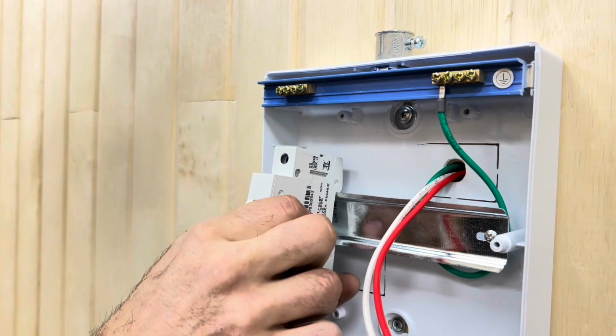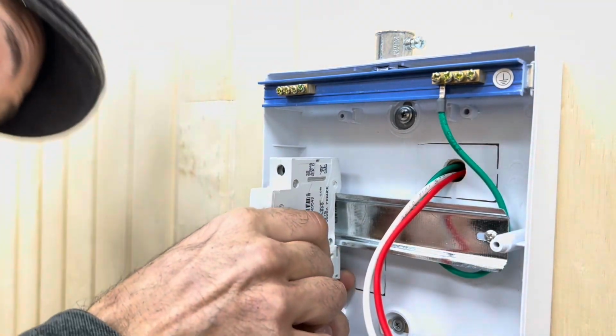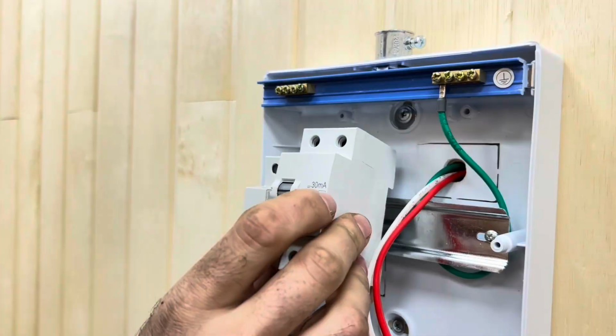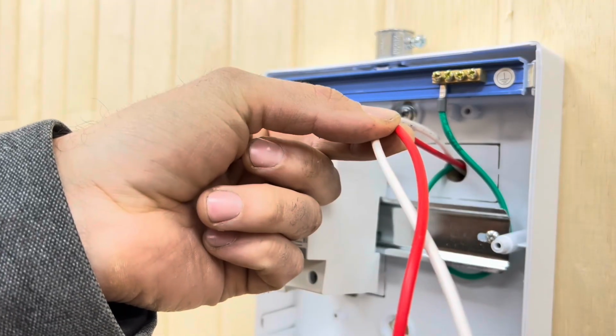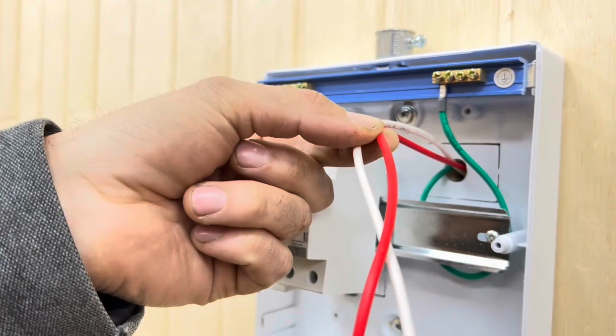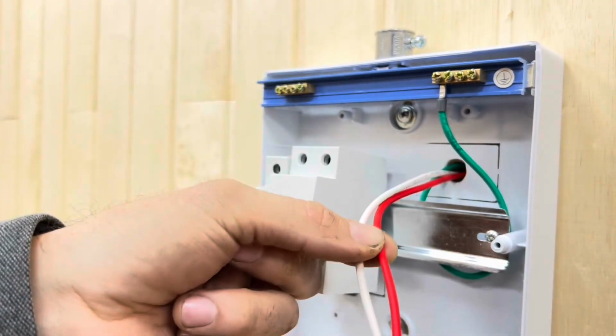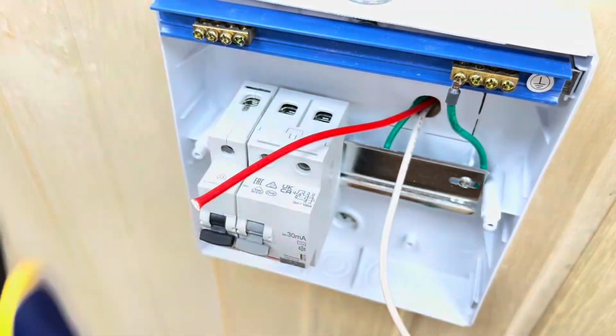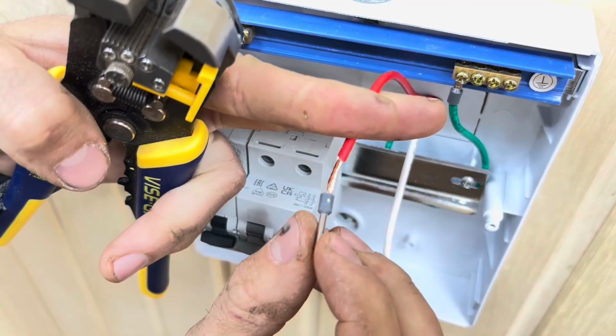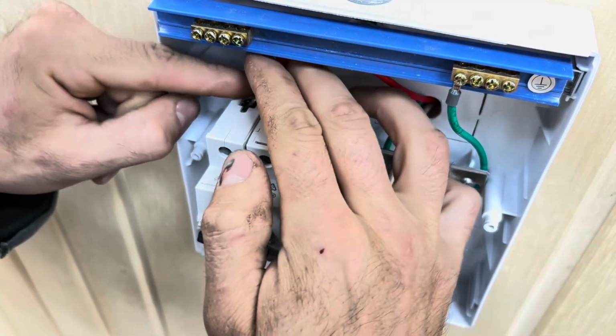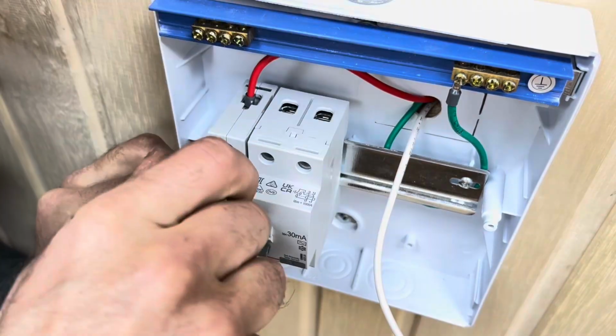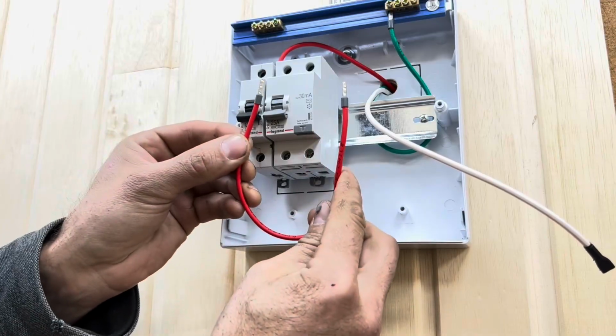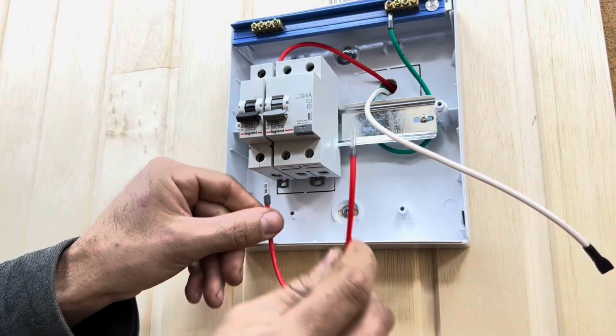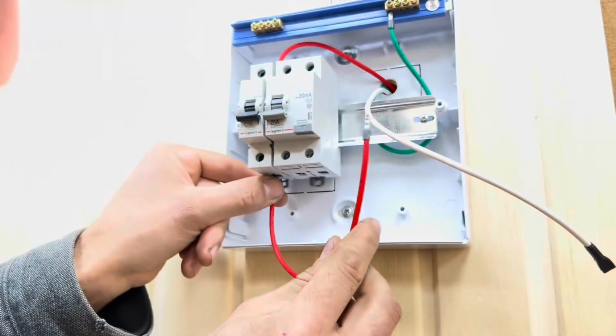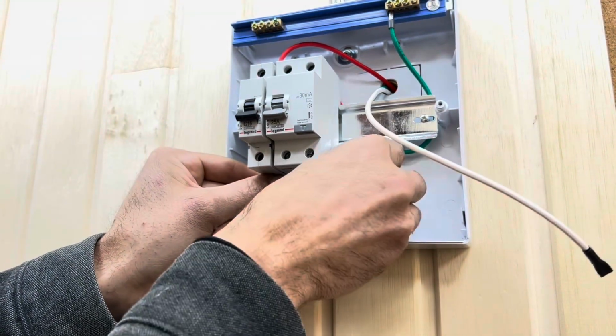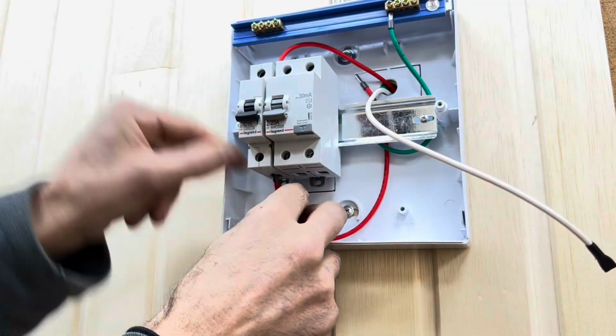Now let's install our switch, thermal magnetic breaker, and our residual current device. The circuit breakers in the house are off. There's no electricity in this outlet circuit, so we can work safely. Here, we continue the phase from the thermal magnetic breaker. Down here, there are outlets below. Then we run it back here so everything stays organized and we put the phase back in.